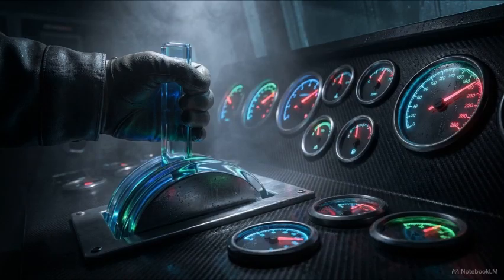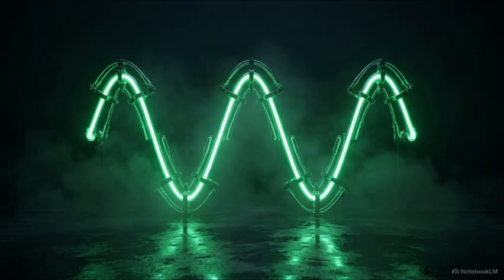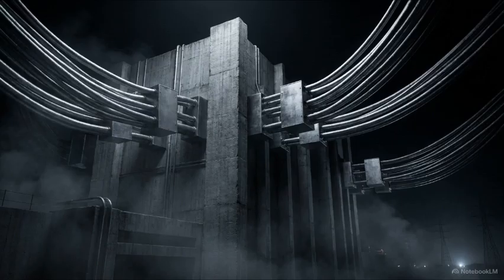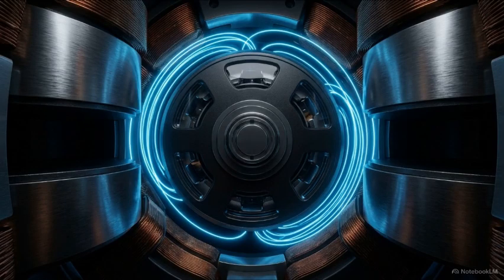Plant operators also use a technique called over-excitation. By pumping extra field current into the rotor, they drive up the internal induced voltage, creating an immediate buffer of stability. Before a single watt of power ever hits the transmission lines, the physical dimensions and magnetic fields of the generator have already been configured to maximize stability.